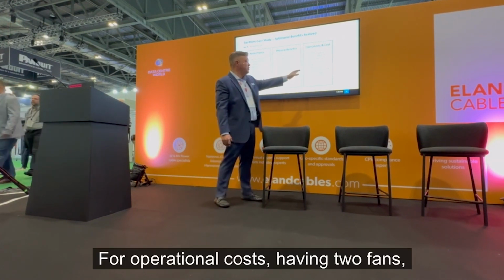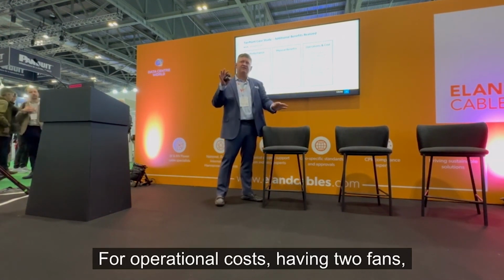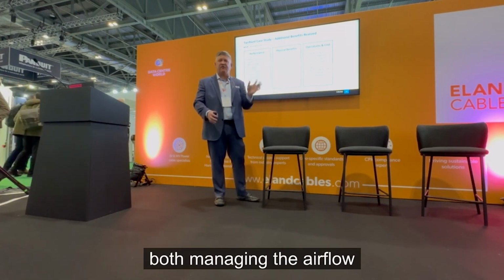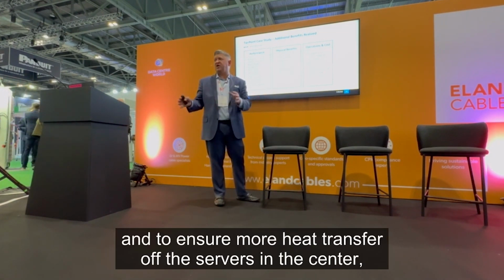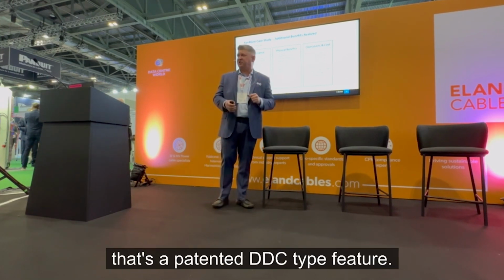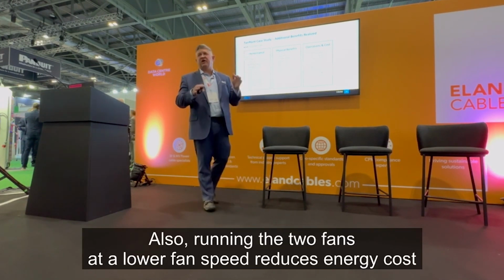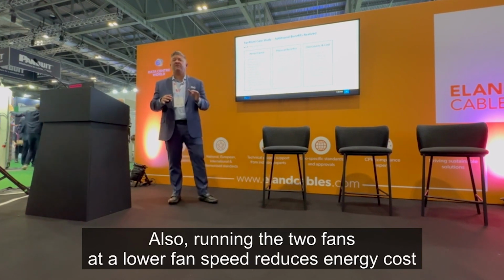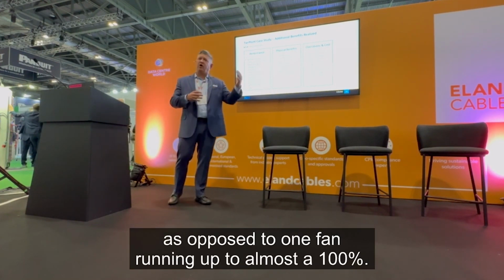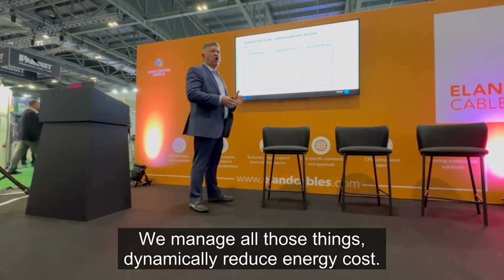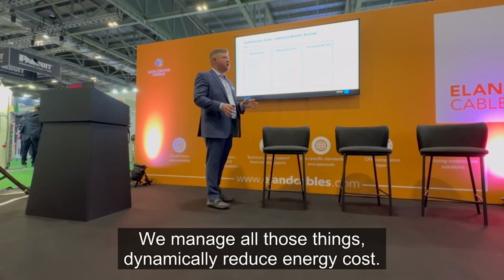That's a significant human resource benefit for using an enclosed cabinet system. And for operational cost, having 2 fans, both managing the airflow, helps ensure more heat transfer off the servers in the cabinet - that's a patented DDC type feature. But also running the 2 fans at a lower fan speed reduces energy cost, as opposed to 1 fan revving up to almost 100%. So we manage all those things dynamically to reduce energy costs.